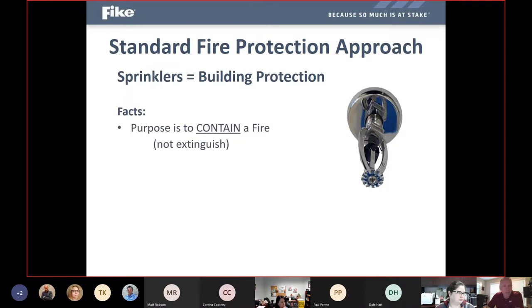The facts are, the purpose of a sprinkler system is to contain a fire and not necessarily to extinguish it. It basically generates almost an umbrella cascade of water, with the idea being that wherever the heat is the hottest, directly underneath the head, melts off that head, and it starts spraying water all the way around to surround where that hottest element of the heat generation is occurring, just to saturate everything around where the fire is actually taking place so it cannot spread. So we try to contain the fire to where it may have originated. Eventually, it will extinguish the fire just because there will be so much water in the area. It may end up accumulating and flooding over top of the surface of whatever is burning. But the main purpose of sprinkler systems is not necessarily to extinguish a fire, but to contain it and prevent its spread to the rest of the facility or the building.